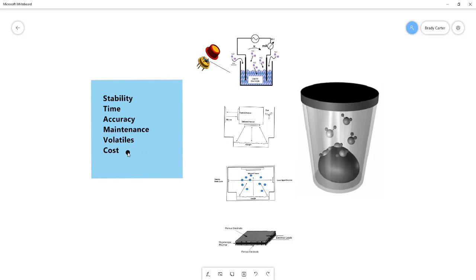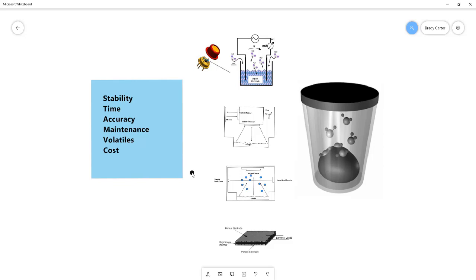And then finally with cost, each of these instruments have a range of instruments available that cover the cost range from low to high. So that it's not as big of a distinguishing factor. Although the TDL tends to be the most expensive technology while the capacitance method is the cheapest technology, but there are options of each depending on what features they have and the accuracy level within all those price ranges.